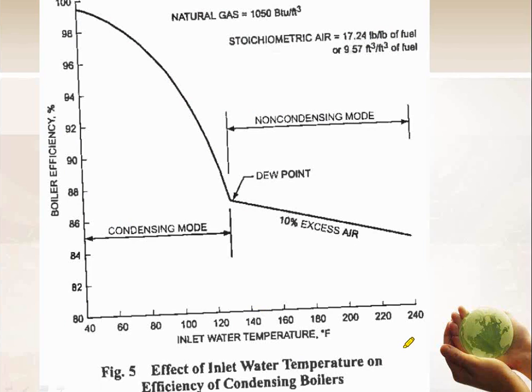For whatever reason, 100 and some years ago, somebody decided all the boiler plants need to operate at 180 degrees. So we sized all the piping and radiators for 180 degrees. And we sized all the radiators for a 20 degree delta T. So 180 supply, 20 degree delta T. That means I've got 160 return water. So most plants are operating at that point. So this particular boiler on this generic chart is basically an 86% efficient boiler when it's operating at those normal conditions. And that's fantastic. It's a good boiler.